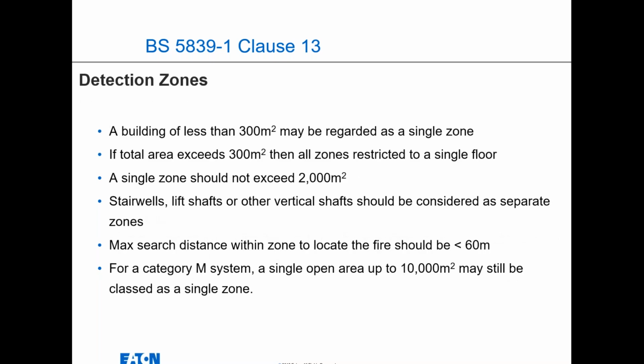You've also got detection zones, and we'll come on to alarm zones in a second. So buildings less than 300 square meters can be regarded as a single zone. But if the total area exceeds 300, then the zones are restricted to floors, and a single zone should not exceed 2,000 square meters. Any stairwells, lift shafts, or vertical shafts, such as risers, should be considered as separate zones, and the maximum search distance within the zones to locate the fire from the point of entry should be less than 60 meters.